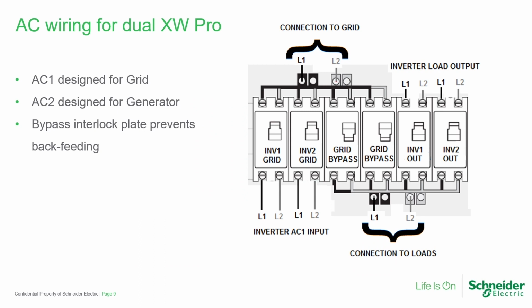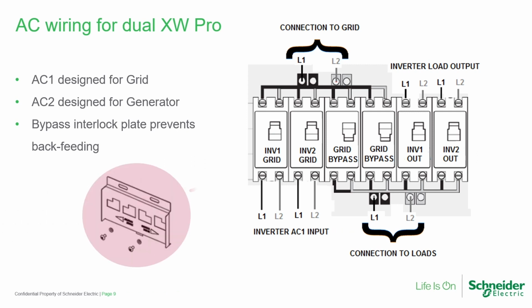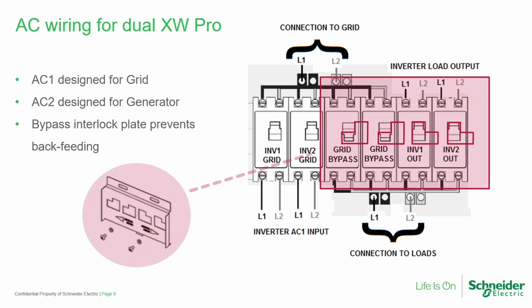A bypass interlock plate ships with the 120-240 breaker kit, which is part number 865-1215-01, for dual inverter systems. There is no bypass interlock plate for a triple inverter system. You can see that it is necessary to turn off the inverter's output breakers before you can slide the plate over to energize the bypass breakers.